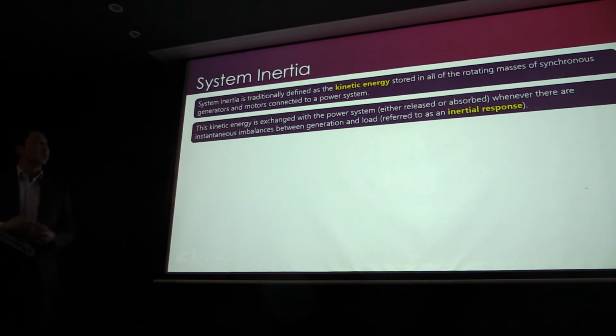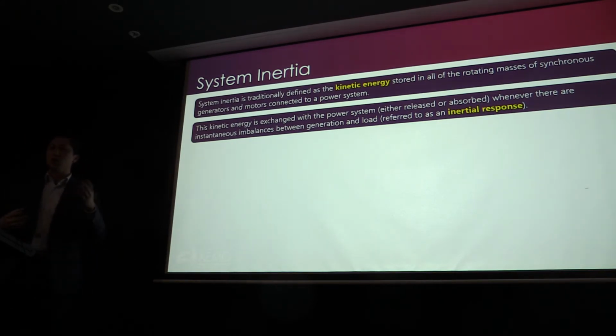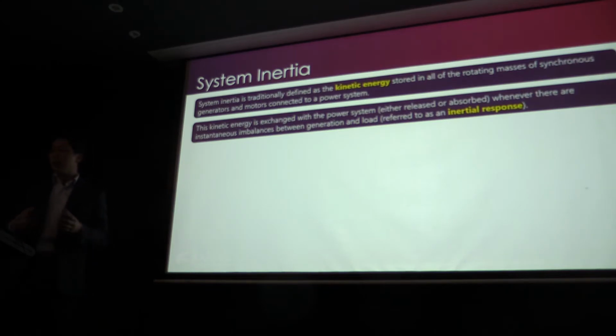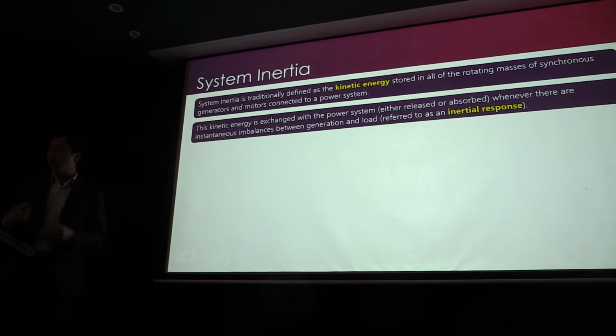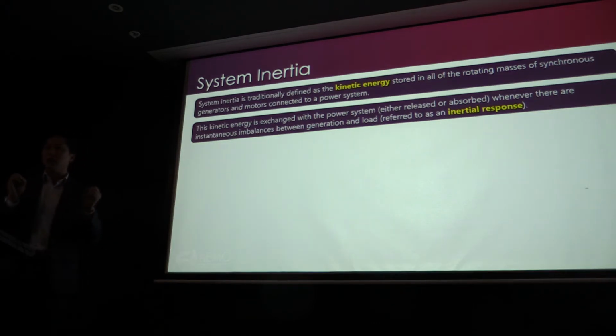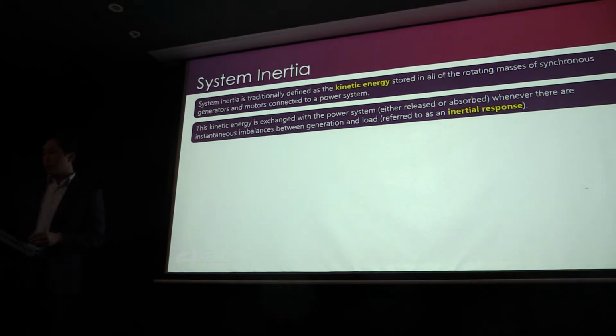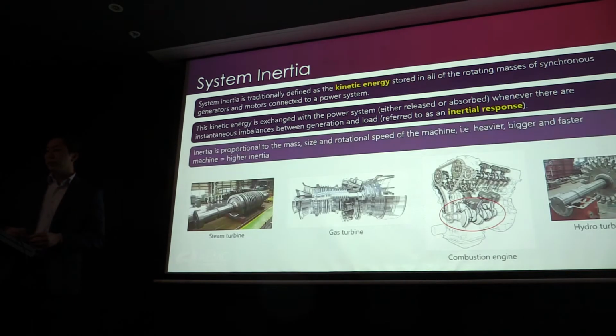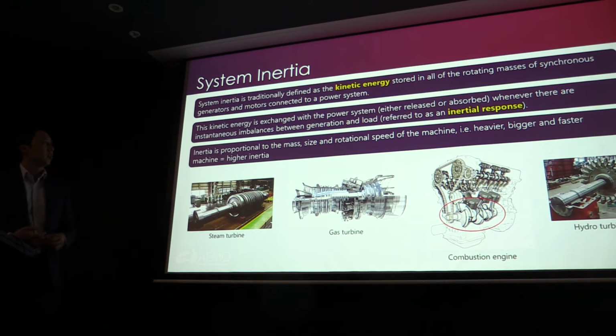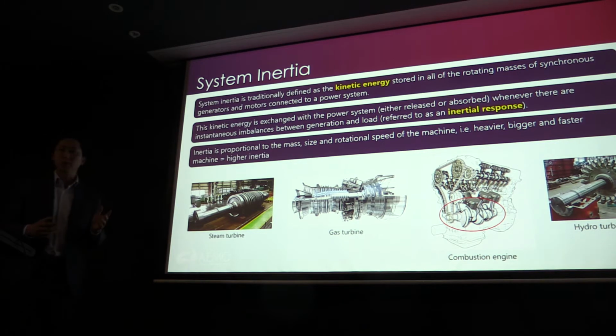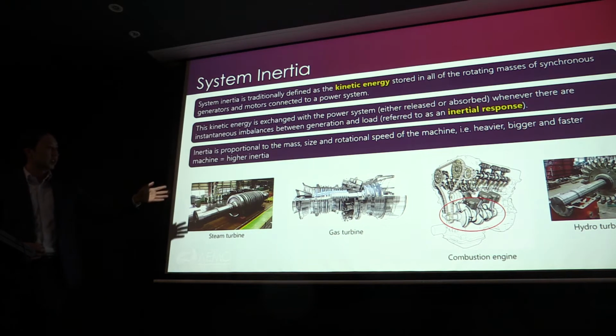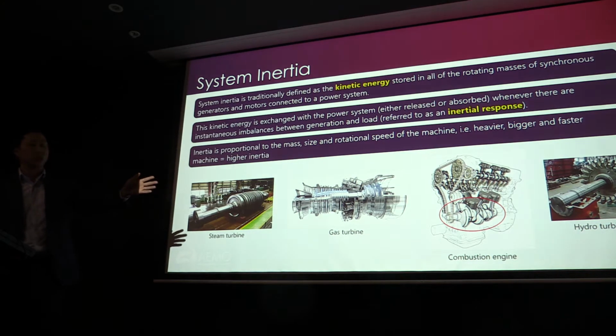It's either released or absorbed whenever there's an instantaneous imbalance in generation and load. So when you have more generation than load, you'll see all the rotors speed up, and when you have more load than generation, you see all the rotors slow down, and then that energy is released into the system. And you call that the inertial response. So inertia is proportional to mass, size and rotational speed of the machine. So a heavier, bigger, faster machine has a higher inertia. And so you can see some examples here. Big machines like steam turbines and gas turbines, small machines like combustion engines, which might have much lower inertia, and hydro turbines somewhere in the middle.